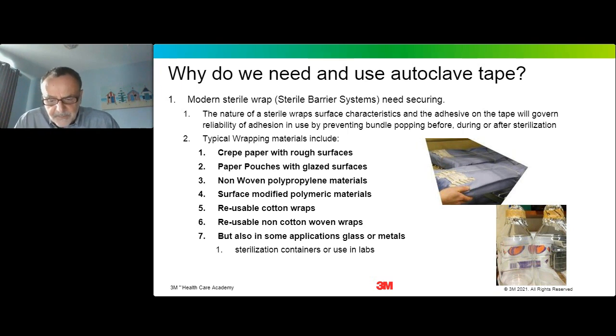So similarly, the adhesive must not only stick when it's first applied, but also over many months of storage. And it should also stick when it's cold, so immediately after you've wrapped your instrument sets, but also, obviously, when it's hot in the steam sterilization cycle, which typically runs at 132 degrees C. So for the autoclave tape manufacturer, these factors present quite some challenges in designing the adhesive that would be used on the tape to enable it to stick to the many surfaces that are going to be used, and to be able to stick when it's cold, but also when it's hot.